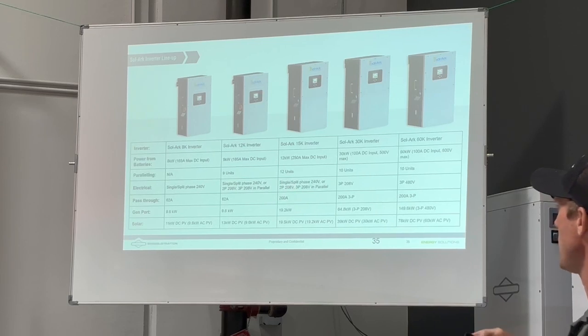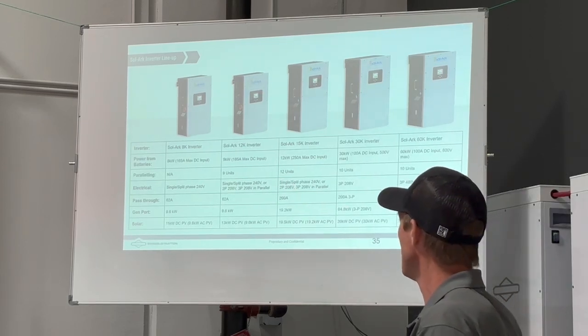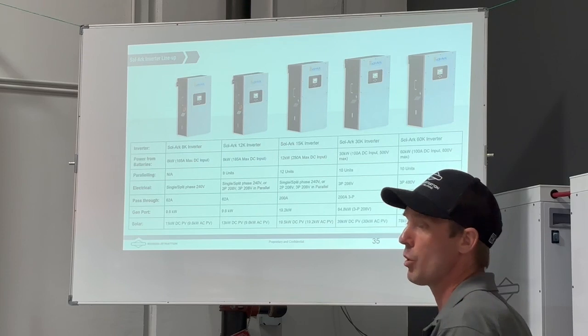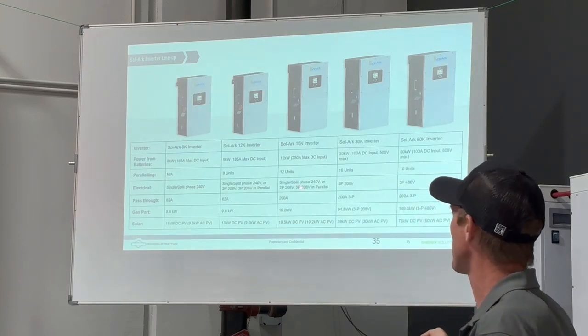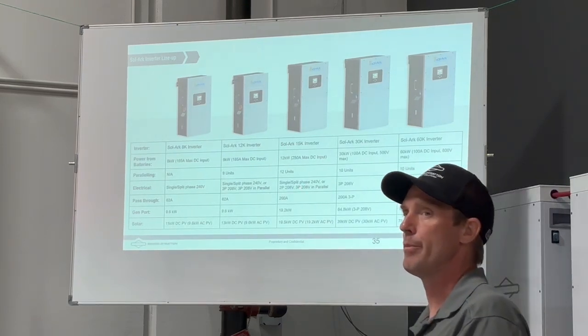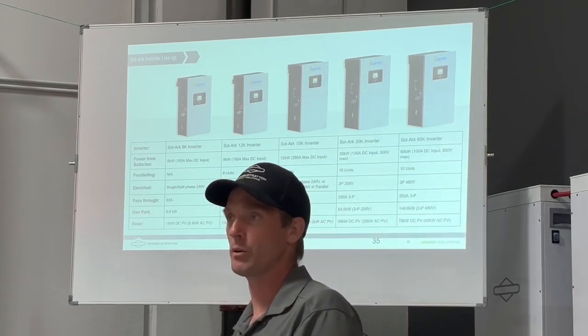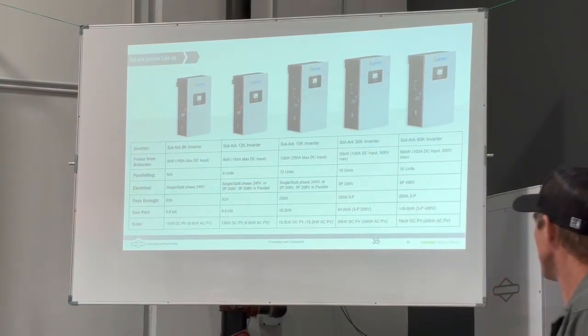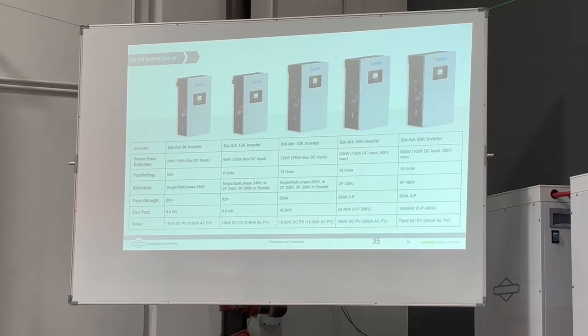Also, you can do split phase, you can do single phase, you can do two-phase 208, or with more inverters, you can do three-phase 208. It's only Y configuration. You can't do delta with multiple inverters. But you can do delta if you just create Y and use a transformer to transform back to delta. And you can even do, is anybody doing any of that anyway? All right, well, if you do the delta, you can actually do delta with a wild leg as well with a transformer. So basically you can do just about any of it.